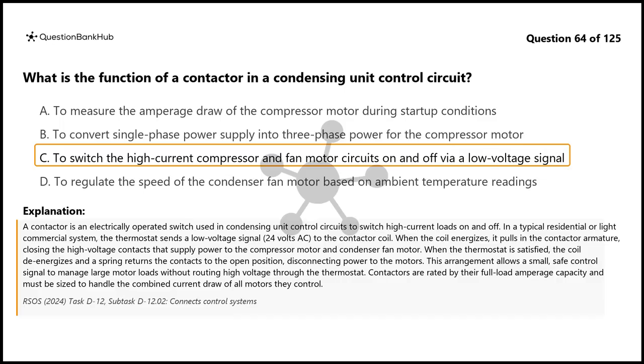When the thermostat is satisfied, the coil de-energizes and a spring returns the contacts to the open position, disconnecting power to the motors. This arrangement allows a small, safe control signal to manage large motor loads without routing high voltage through the thermostat. Contactors are rated by their full load amperage capacity and must be sized to handle the combined current draw of all motors they control.